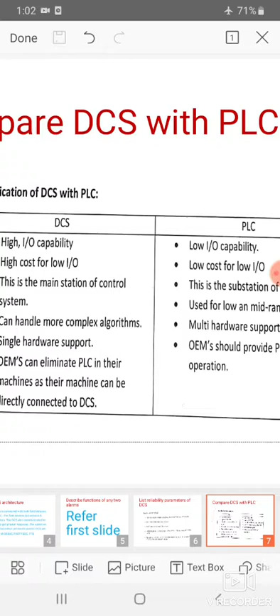Then coming to the comparison between DCS and PLC. The DCS has high IO capability compared to PLC, where PLC has low IO capability, that is, the capability to scan the input and actuate the output. High cost for high IO in DCS, low cost for low IO in PLC. DCS is the main station of the control system. The PLC is the substation for the control system. The DCS can handle more complex algorithms, whereas the PLC is used for low and mid range algorithms.